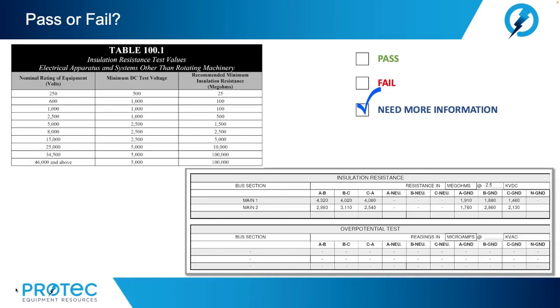And we obviously had seen the correction factor for 1,000 foot nominal runs is necessary in order to get an accurate comparison to Table 100.1. So, let's go based on the readings that are shown here.